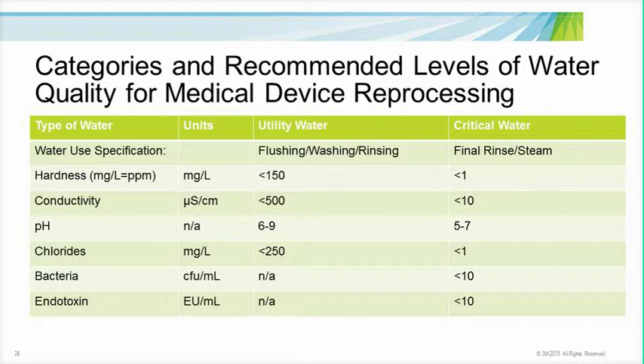The acceptance value for conductivity for utility water should be less than 500 microsiemens per centimeter, and less than 10 microsiemens per centimeter for critical water. The pH for utility water should be between 6 and 9, and the pH for critical water should be between 5 and 7. Utility water should have less than 250 milligrams per liter of chlorides and less than 1 milligram per liter of chlorides for critical water. And probably the most important part of the differentiation between utility and critical water is that critical water should have less than 10 colony-forming units per milliliter and less than 10 endotoxin units per milliliter.